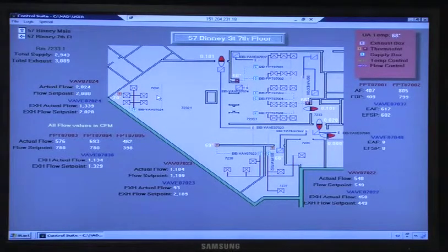I mean, we have all of the ones that are going to go for the air regulation, the AV reg things. Yeah. Pharmacy does not belong to the air regulation business. It belongs to USP 797. It's a totally different thing. Your two TSI devices will look different. Whether we're able to set that alarm or it's physically set on the device will depend on what we get for that device when it gets installed. If that's the case, then it's just free text on there saying what the alarm parameter is, so we can reference it. I'm just speculating. We'll find out when it gets in next week and see how it works.